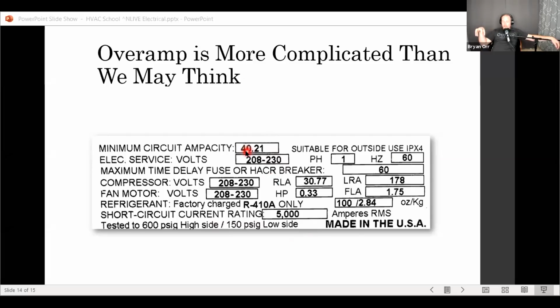So the reason why they allow for it is, one, it's because of starting amps, because starting amps are higher and they don't want to have nuisance trips. So that's why they allow a bigger breaker on a wire that's smaller. Because again, most people would say, well, you've got to put a number 6 wire on it. No, you don't. You may have to based on other factors. But as far as we're concerned, as AC technicians, as long as the wire will handle 40 amps, we can put a 60 amp breaker on it.